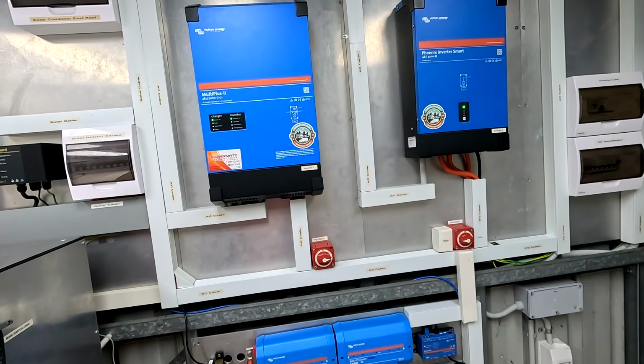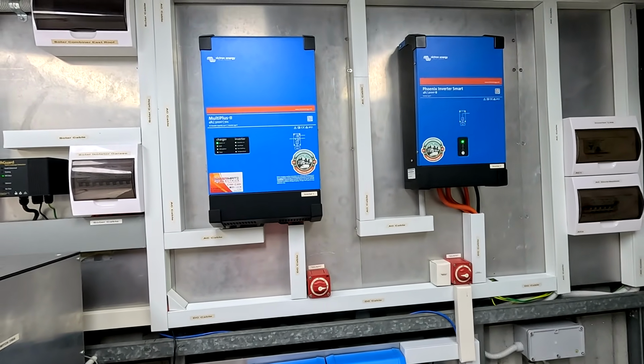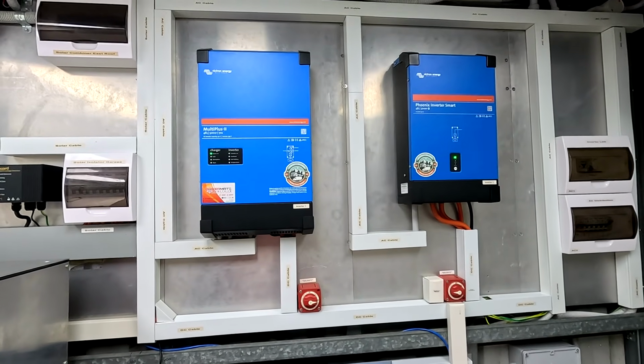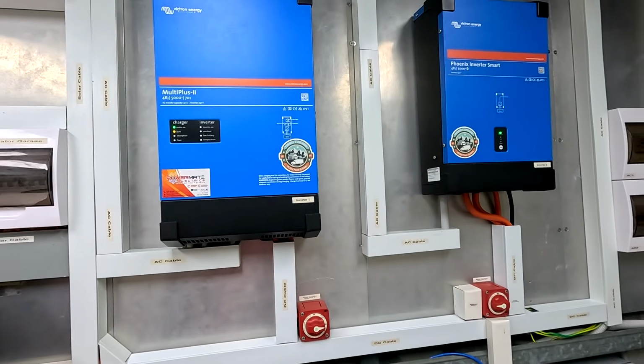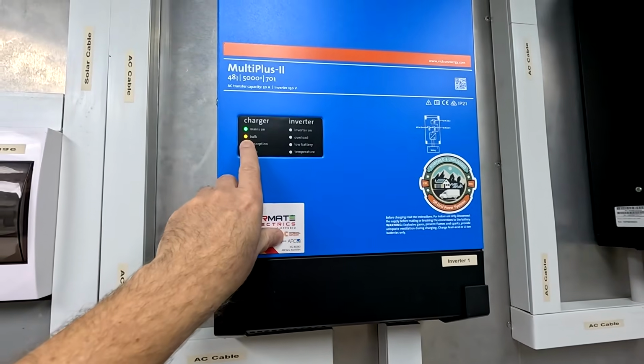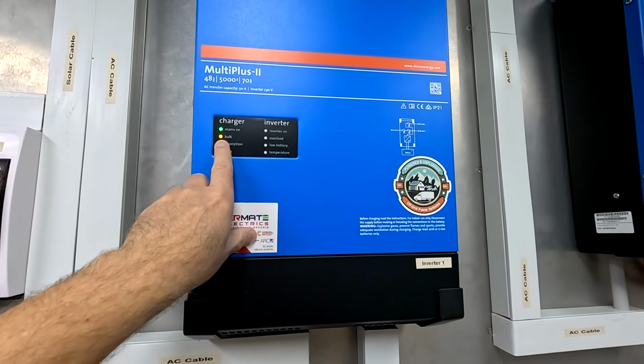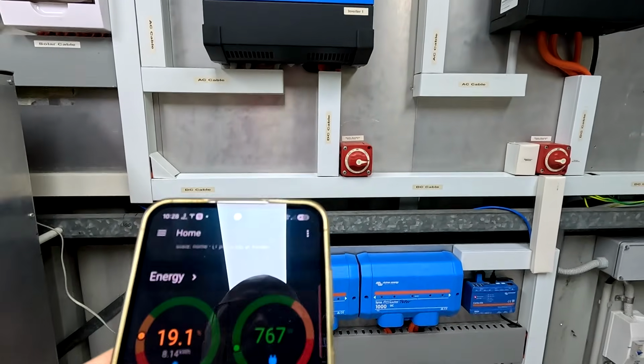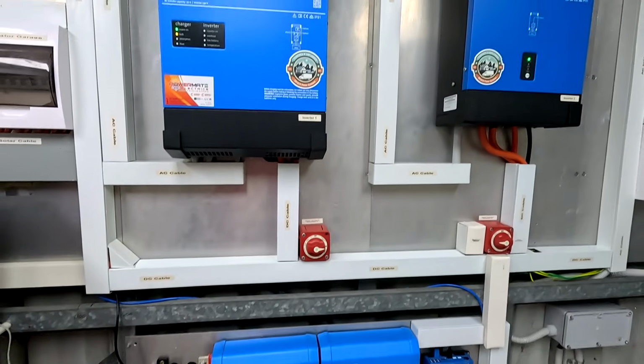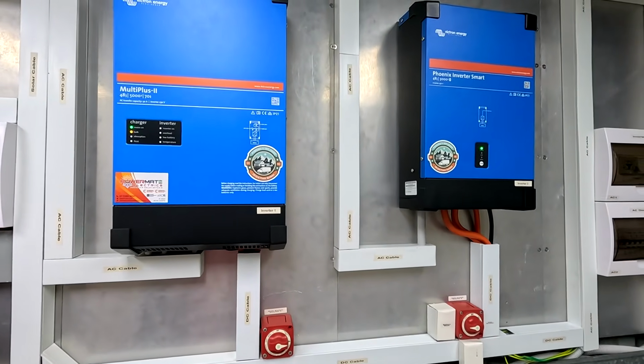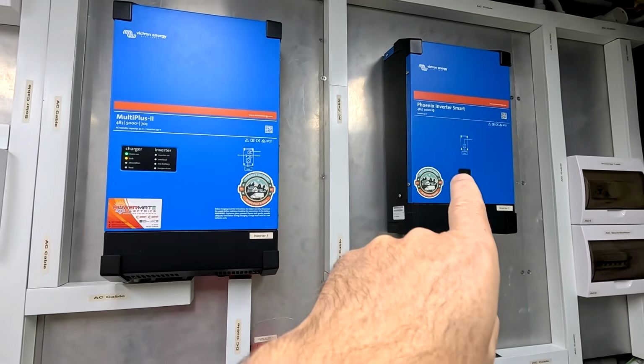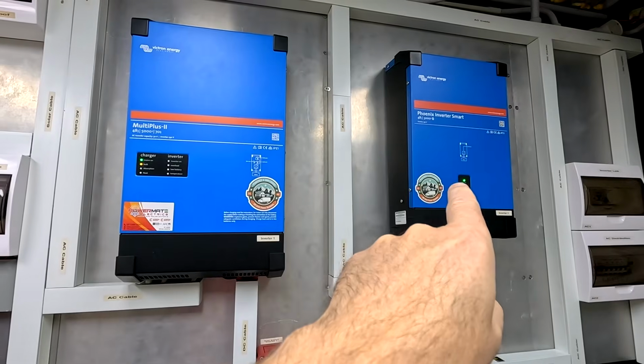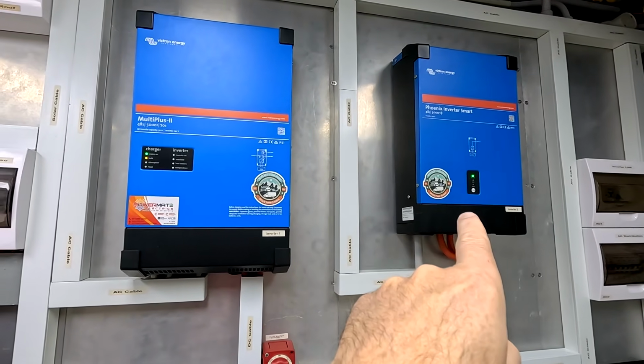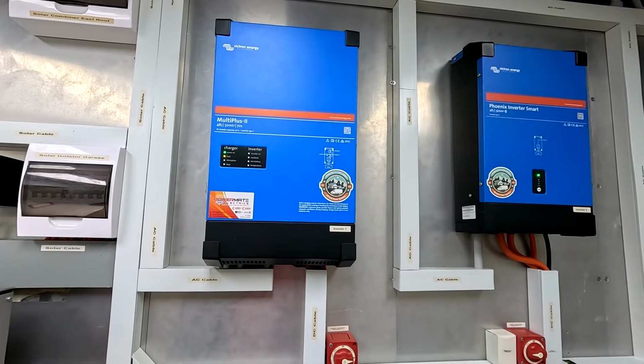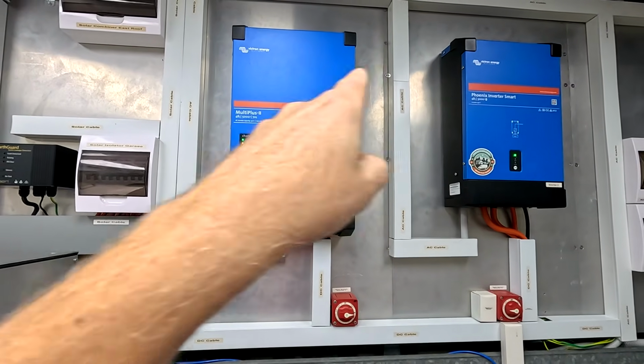Oh yeah, we are now under 2000 watts, so it should take a few seconds and then we should switch over. Let's see if the light flickers in here as well when this happens. Now we've got the situation that the bulb has turned on because the heating of the washing machine or dishwasher has turned off. And we must be using very little power here, 760 watts only, but the Phoenix inverter obviously is still producing power. So this inverter is actually charging the batteries now, but this inverter is getting its energy from the same battery it charges through the multi-plus. So we are now charging in a circle basically.